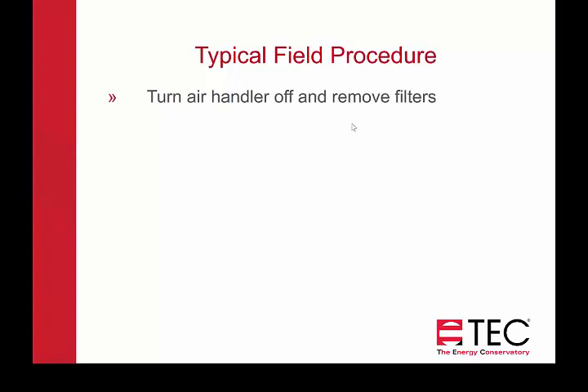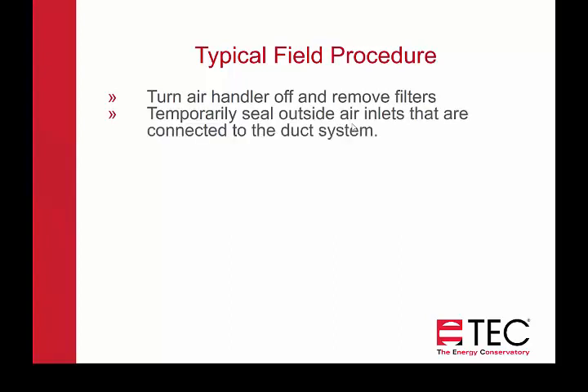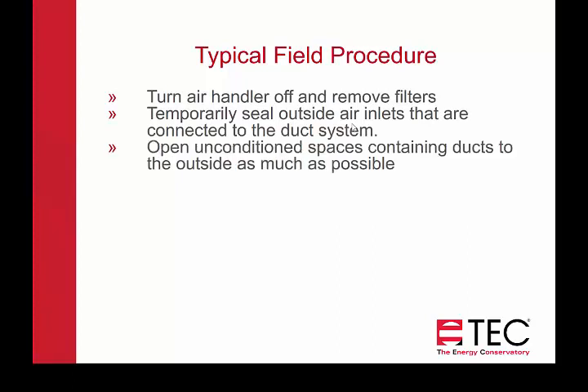The procedure when you're doing a duct leakage test: turn off the air handler and always remember to remove the filters. You'll want to temporarily seal any intentional openings, like an air inlet connected to the duct system — you're trying to measure the unintentional duct leaks. So you'll want to seal off intentional leaks like a pressure intake going to the outdoors connected to a return duct. You'll want to open unconditioned spaces containing ducts to the outside as much as possible — this is also the case when doing duct blaster tests. If you've got a vented crawl space, make sure the vents are open, or if there's a door in the crawl space, open the door.